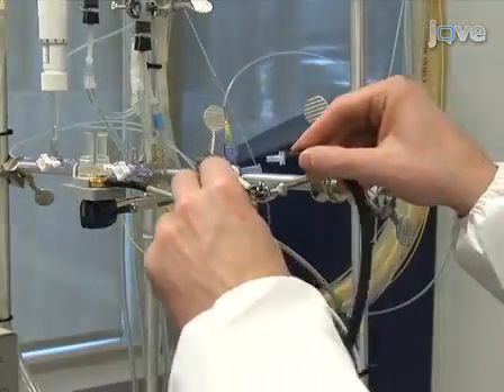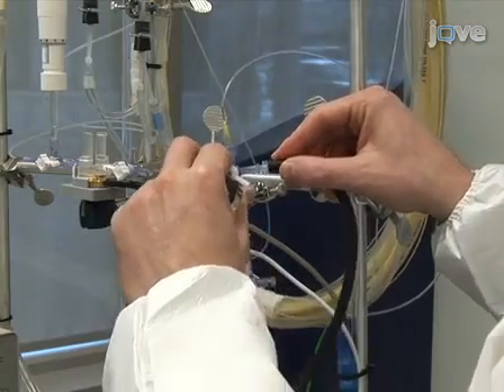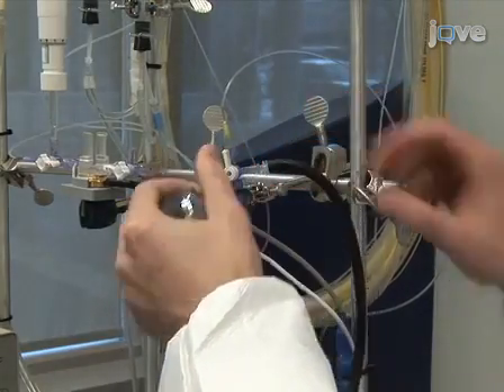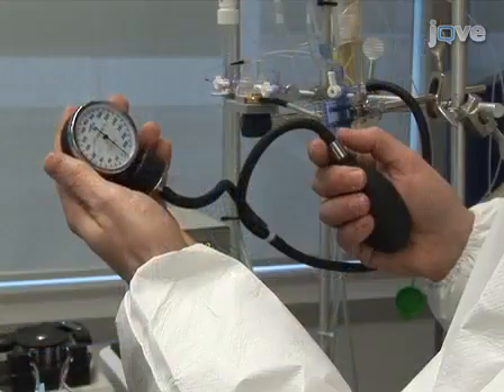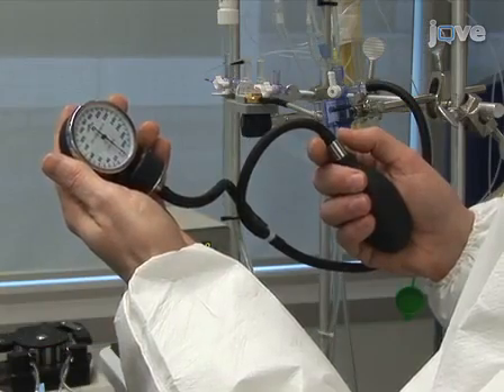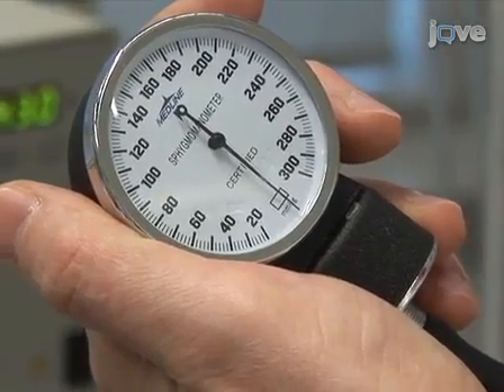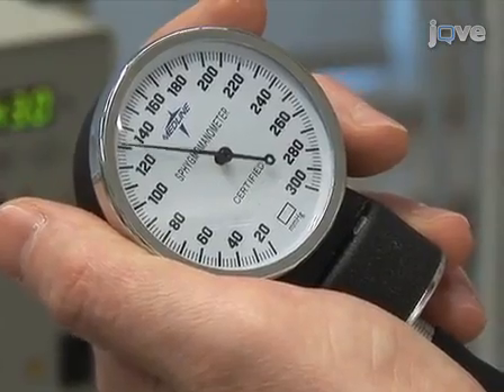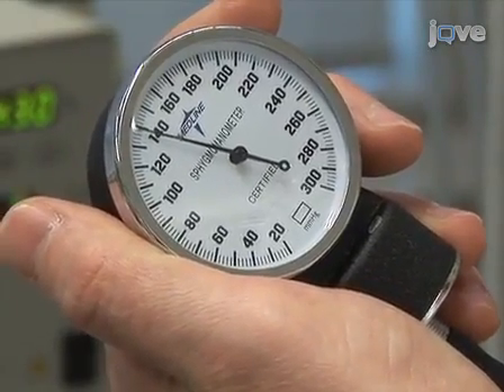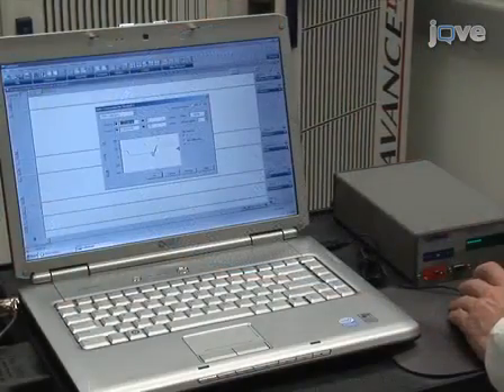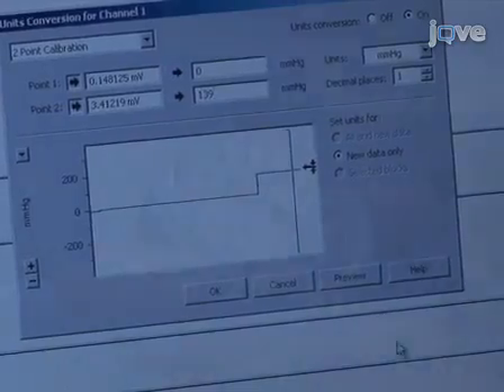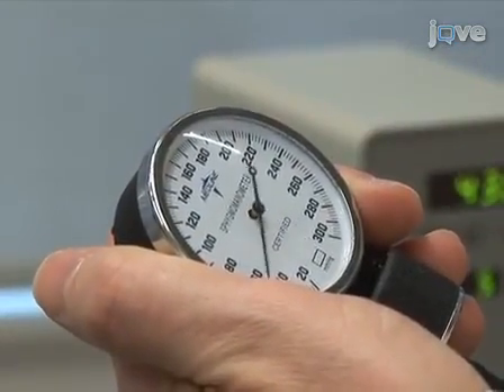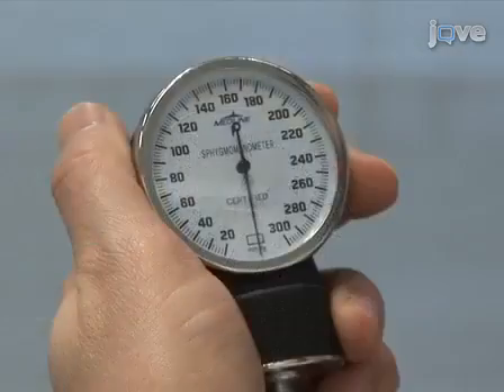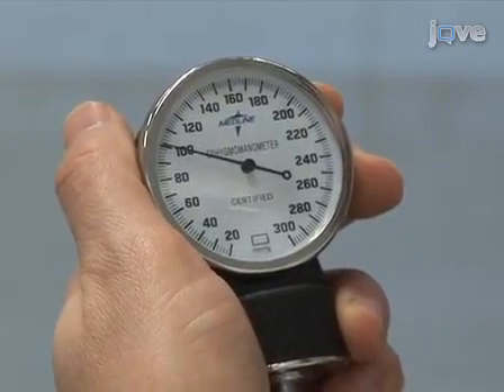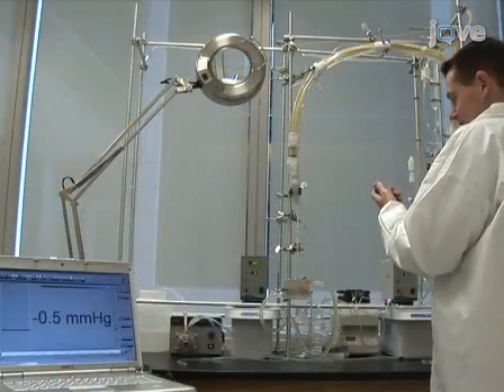Prior to the start of the experiment, calibrate the pressure transducers with a standard sphygmomanometer. First, place no pressure into the transducer to zero the calibration. Then, inflate the sphygmomanometer to a high pressure. Enter this value into the computer program. Then, confirm that the pressure transducers have been adequately calibrated by inflating the sphygmomanometer to known pressures and verifying them on the computer screen.